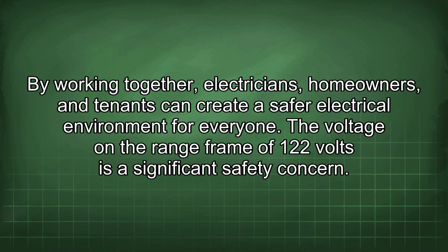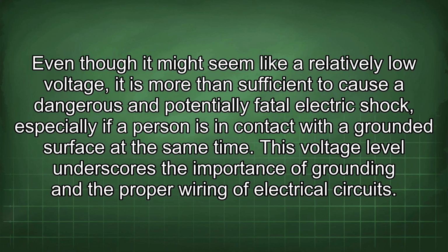The voltage on the range frame of 122 volts is a significant safety concern. Even though it might seem like a relatively low voltage, it is more than sufficient to cause a dangerous and potentially fatal electric shock, especially if a person is in contact with a grounded surface at the same time. This voltage level underscores the importance of grounding and the proper wiring of electrical circuits.